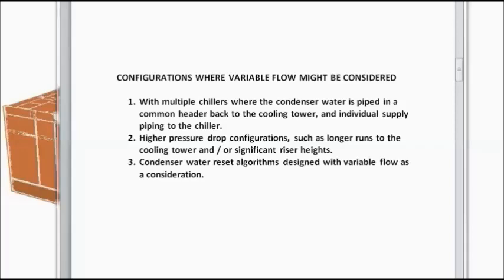And another consideration is that if you are using condenser water reset, then the reset algorithm should be designed with variable flow as a consideration.